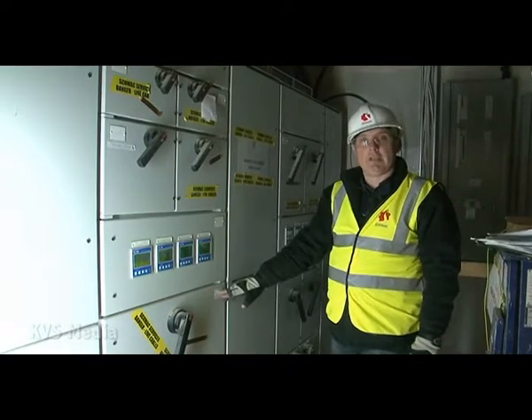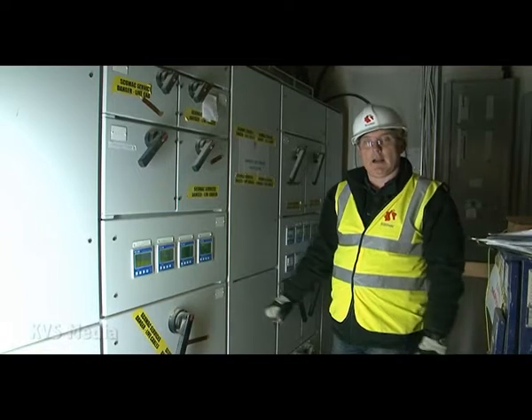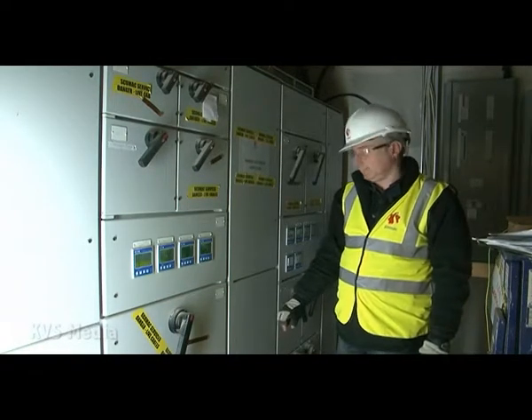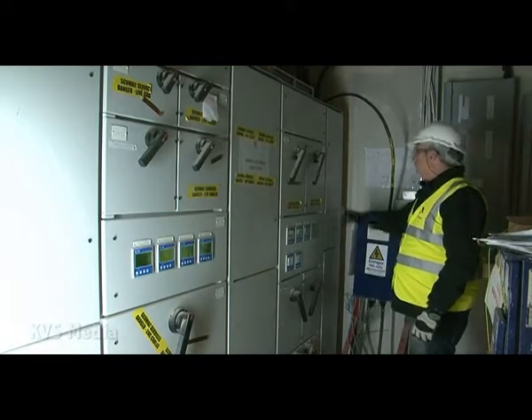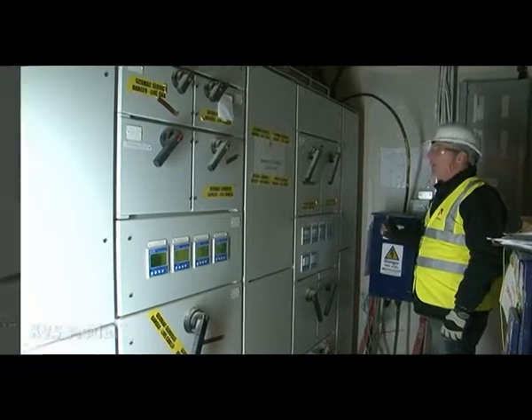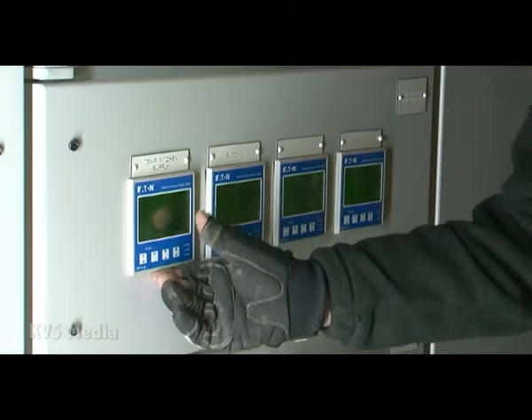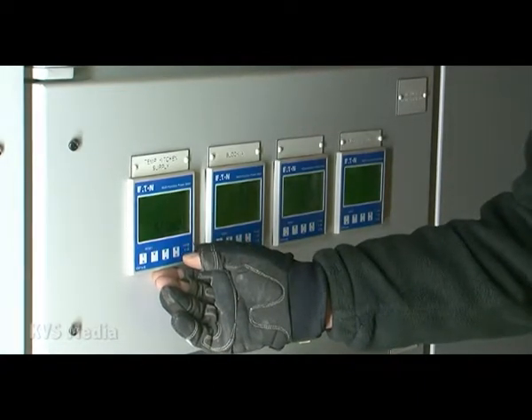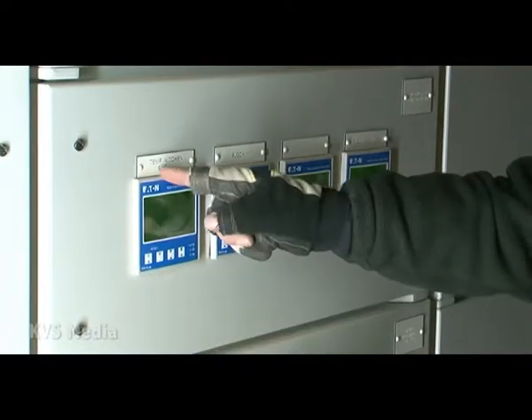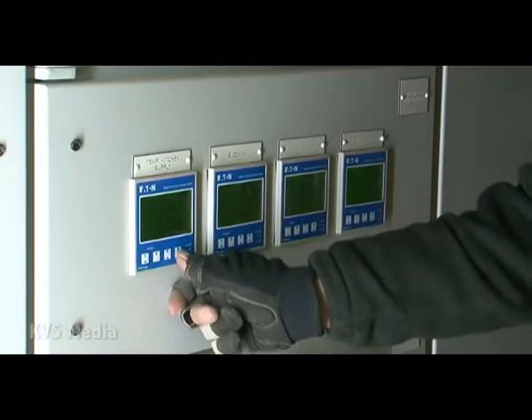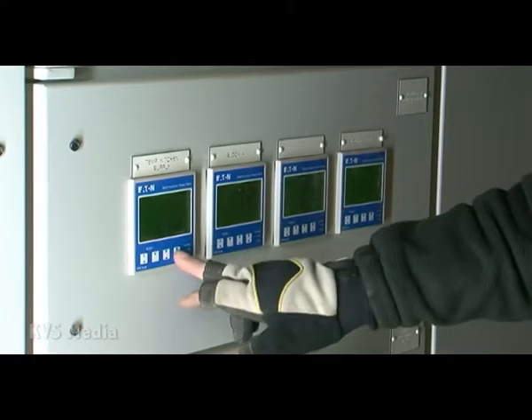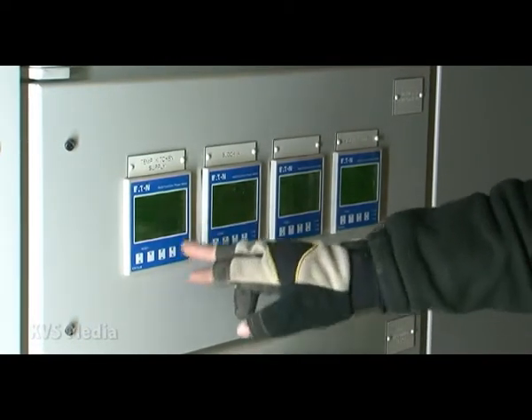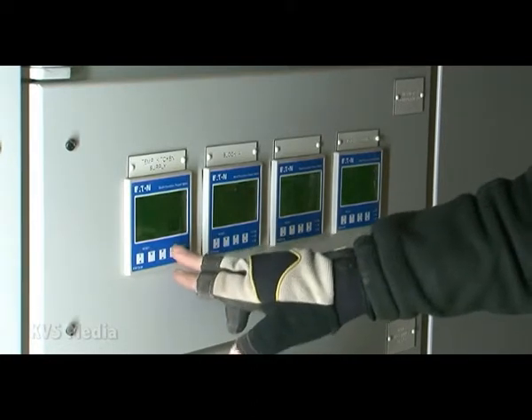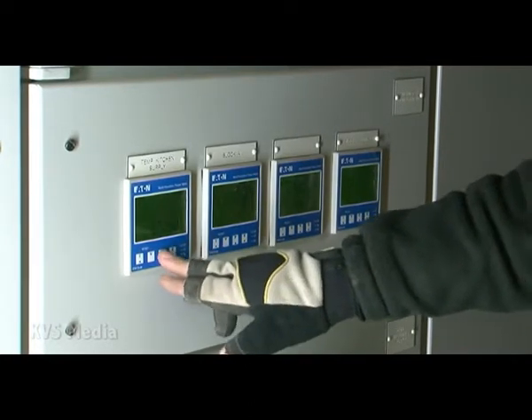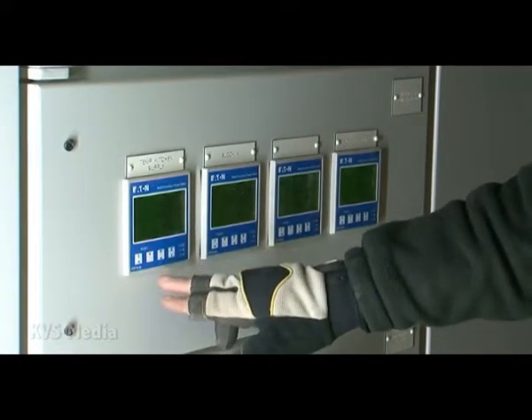This is fed from the GRP room, which we've just seen, over behind Walworth House. All the local boards come off this for this area. We have a typical multi-function meter for all the services that are off this panel. Each area has its own meter, whether it's Block A, kitchen or annex. And you scroll through, just going through the keys, it tells you quite clearly the kilowatt hours. Scroll down, it tells you the current run and what amperage is per phase, the kVA for each phase.